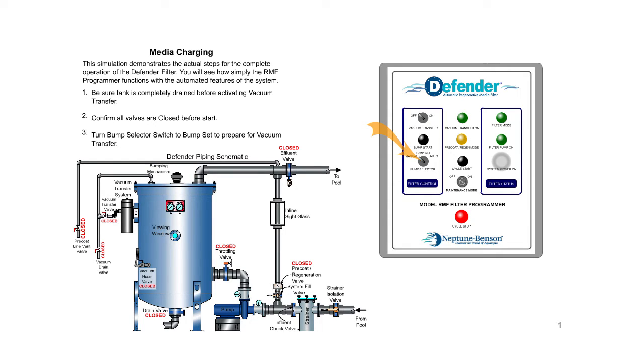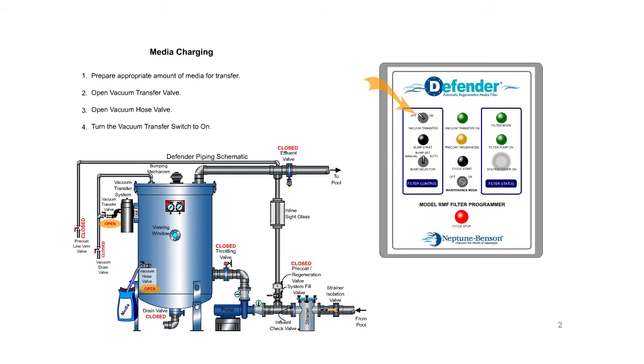Media charging. Be sure tank is completely drained before activating vacuum transfer. Confirm all valves are closed before start. Turn bump selector switch to bump set to prepare for vacuum transfer. Prepare appropriate amount of media for transfer. Open vacuum transfer valve. Open vacuum hose valve. Turn the vacuum transfer switch to on.